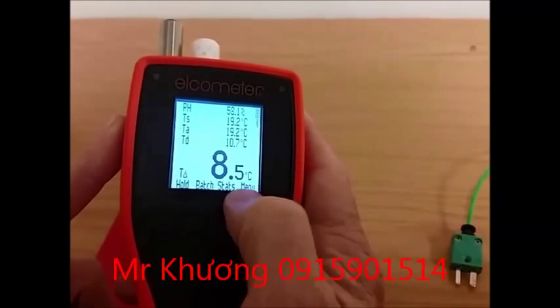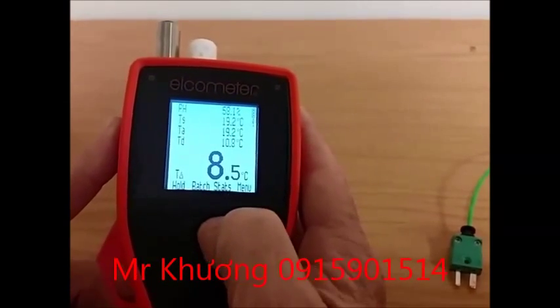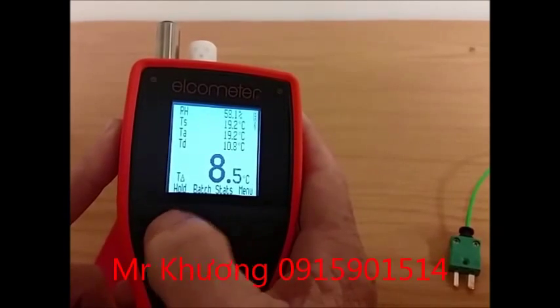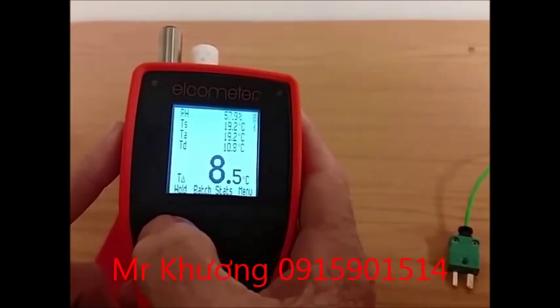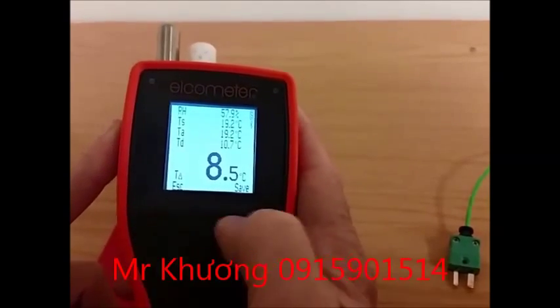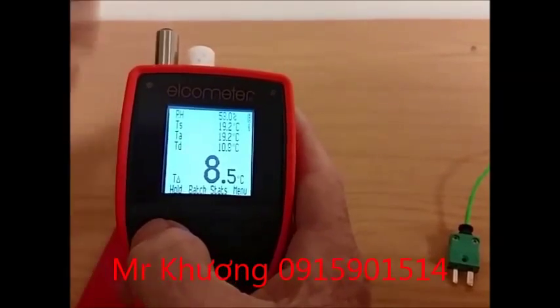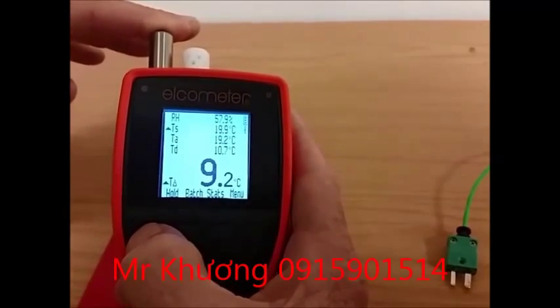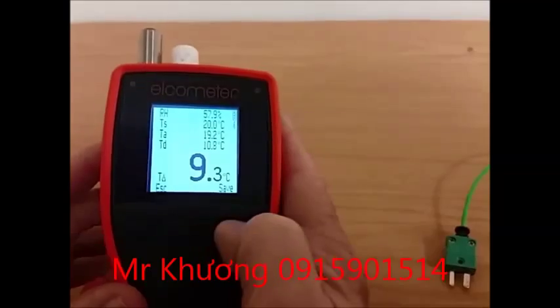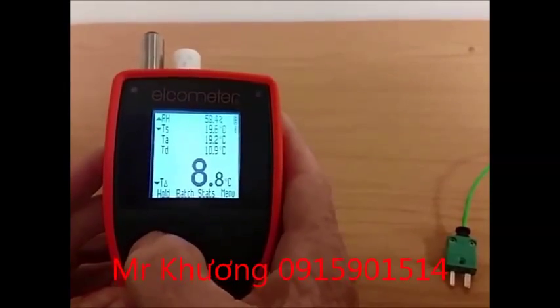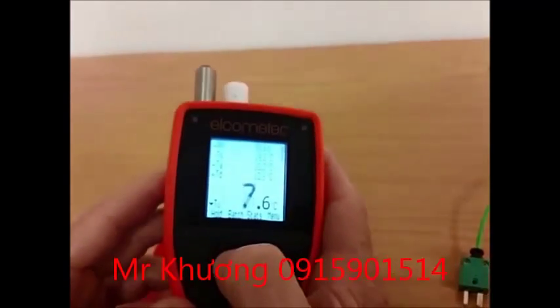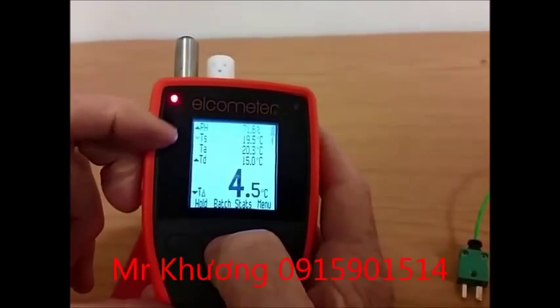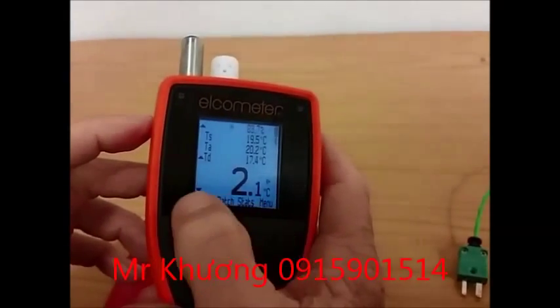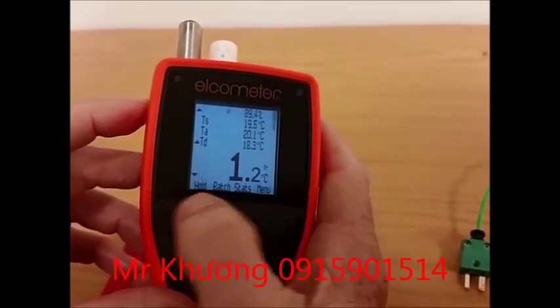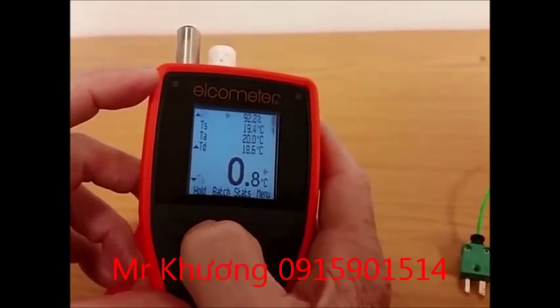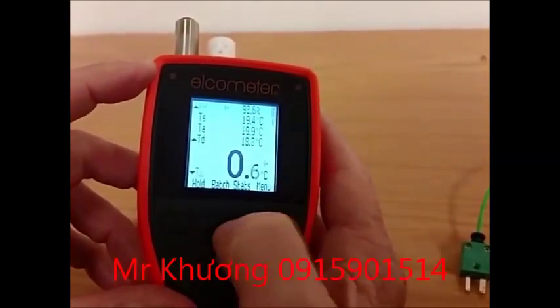So covering the next option, we've gone through everything under menu, under stats. Okay, well let's actually just take a couple of readings. So we've got hold and save. So it will record those readings there. If we increase the surface temperature, hold, save that, and you can blow. And again, the readings, you can see arrows going up and down, adjusting. As soon as this gets below the threshold, which is 3, it will alarm. You can hear it alarming and the red light flashing. So you can hold and save that.